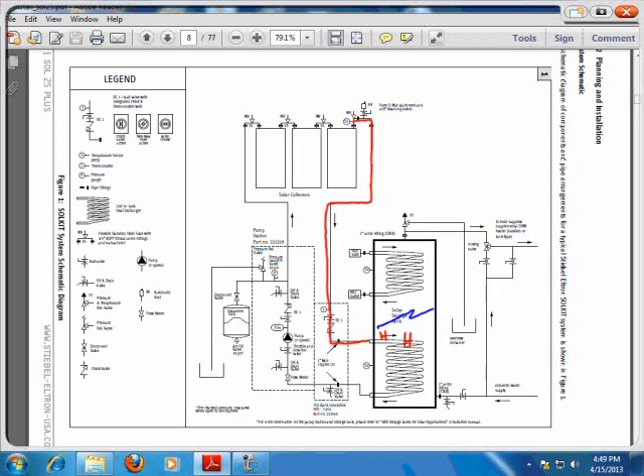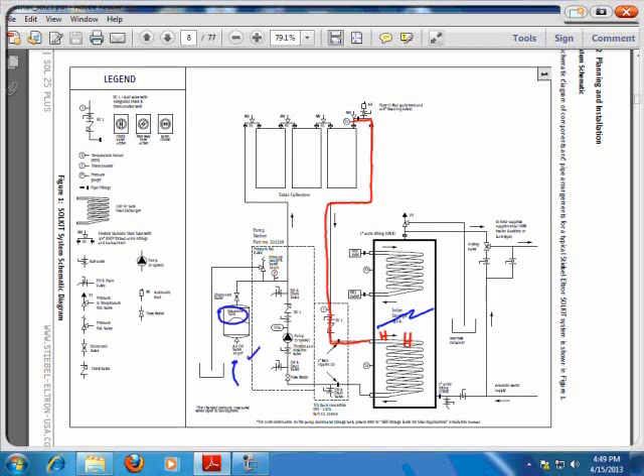And so in a video past, we talked about the expansion tank sizing, and notice that the expansion tank size here was that Extrol X15 size. And then what we had was we actually said, and it's difficult to see on the schematic, but we are actually leaving the fill pressure at actually 45 psi. So that's what the bladder is going to show you.